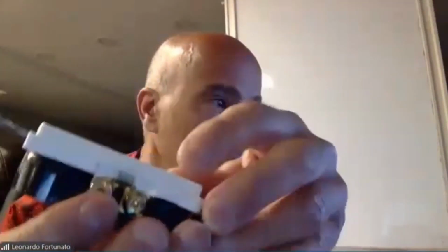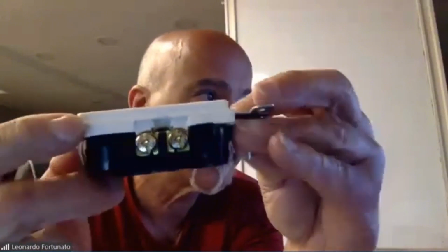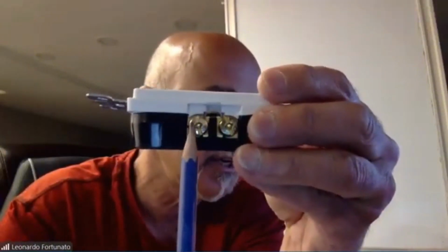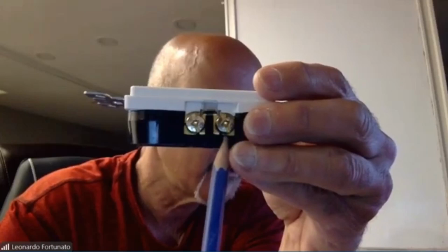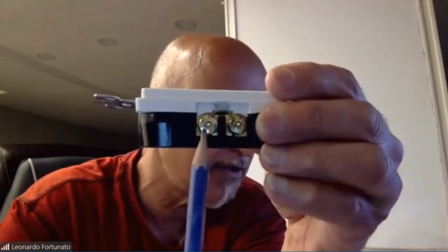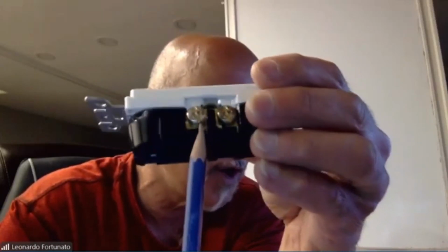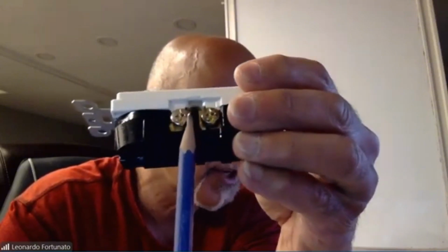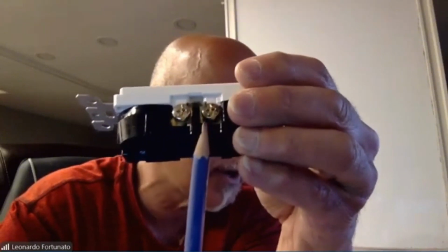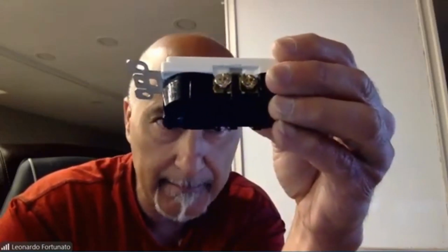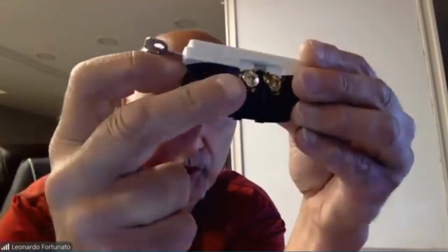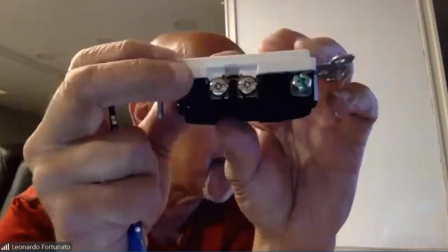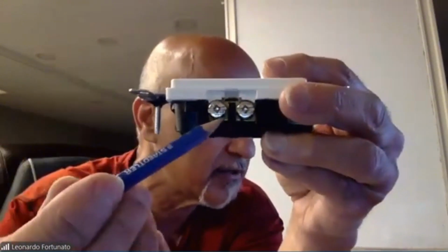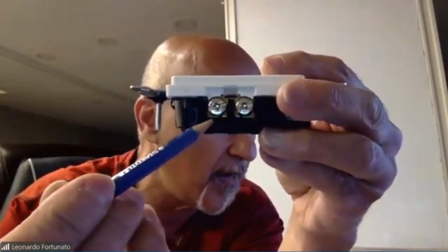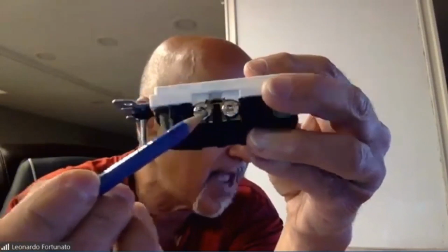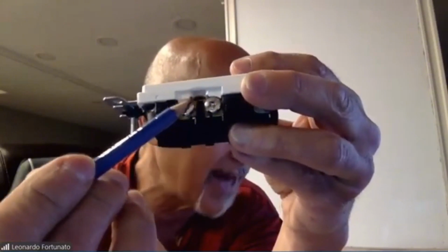As you can see over here, we are looking at the hot side of a receptacle. You can see there is a screw here and a screw here. There's a little plate behind each screw. If you notice, this plate has a tab in the middle that jumps over to this plate - do you all see that? If we turn this around to the neutral side, you'll see it does the exact same thing. We've got our silver screw here and a silver screw here, and underneath we have a little plate, again interconnected with that little tab.